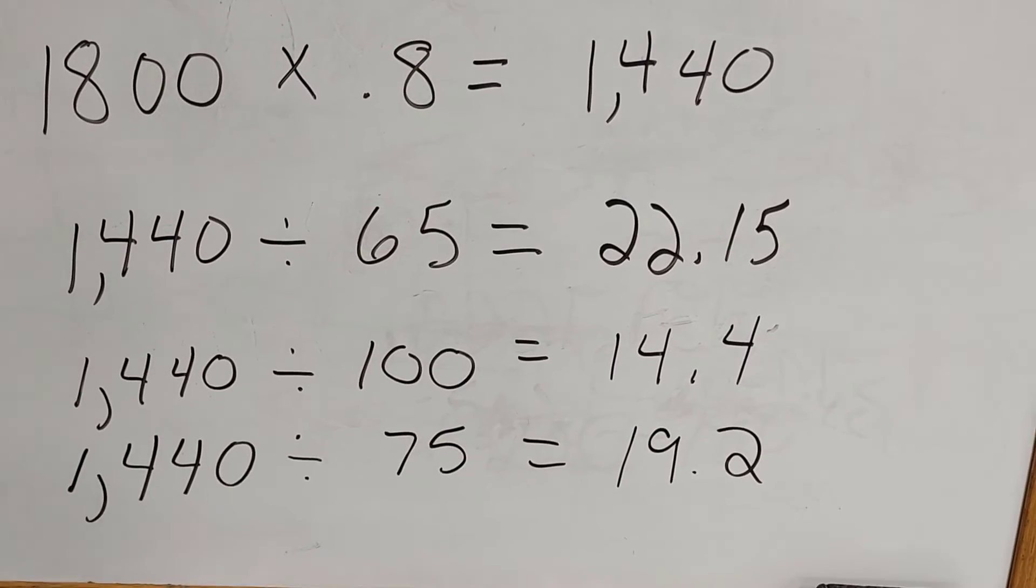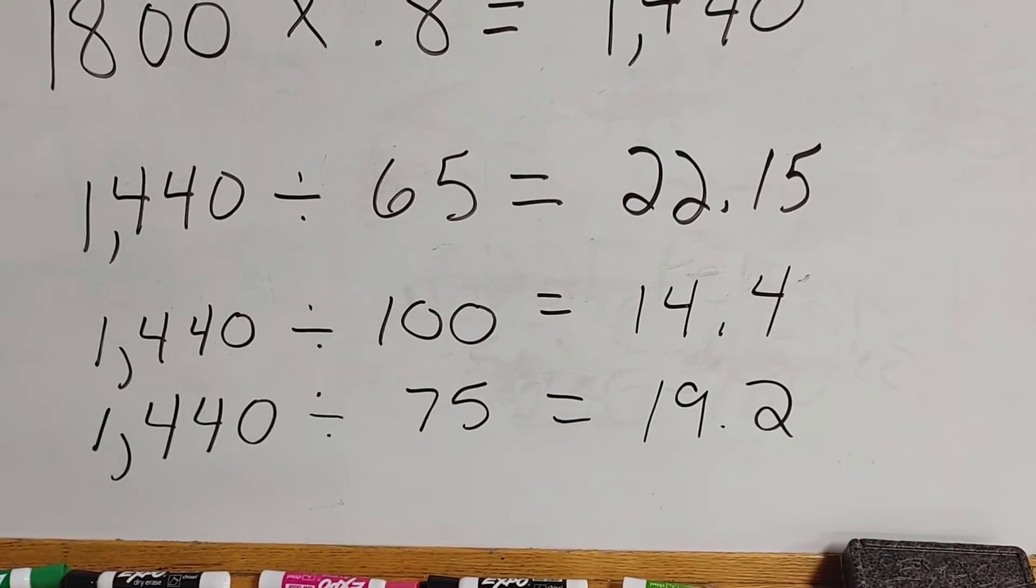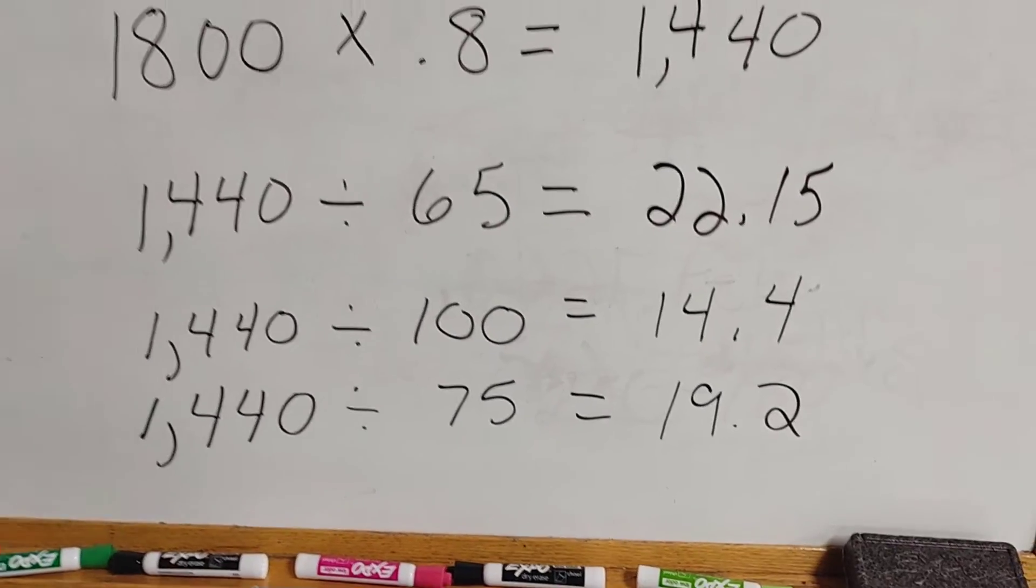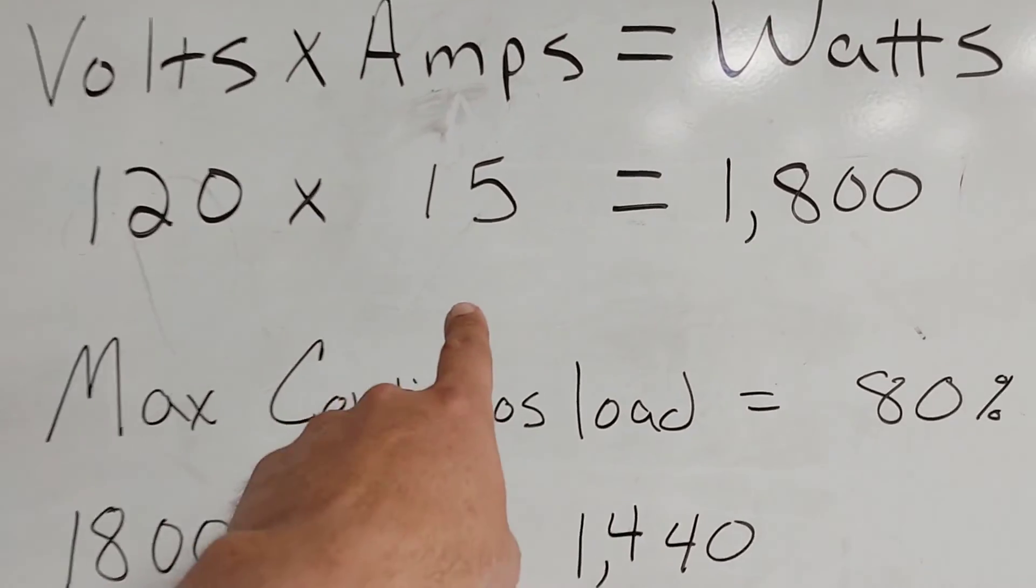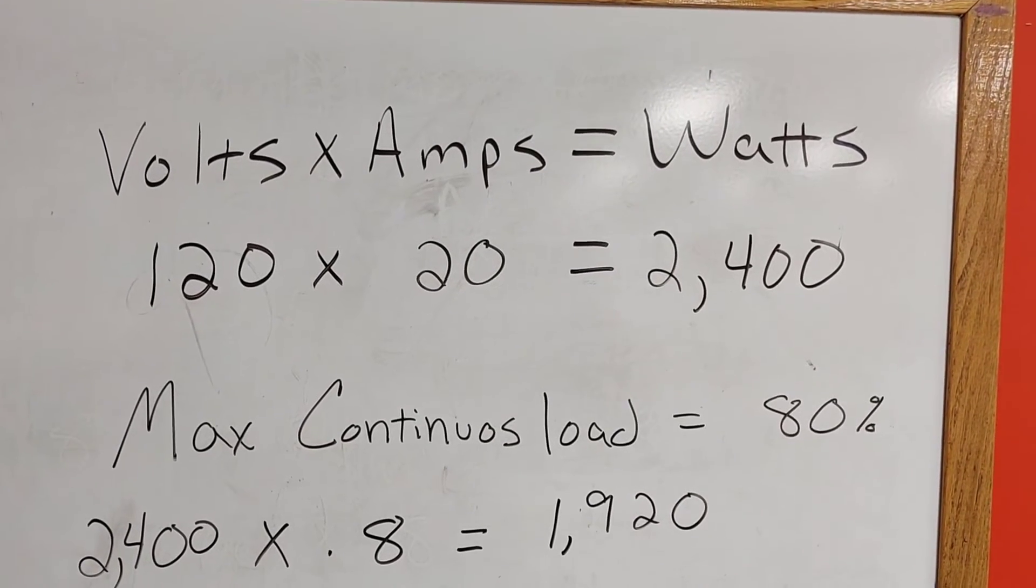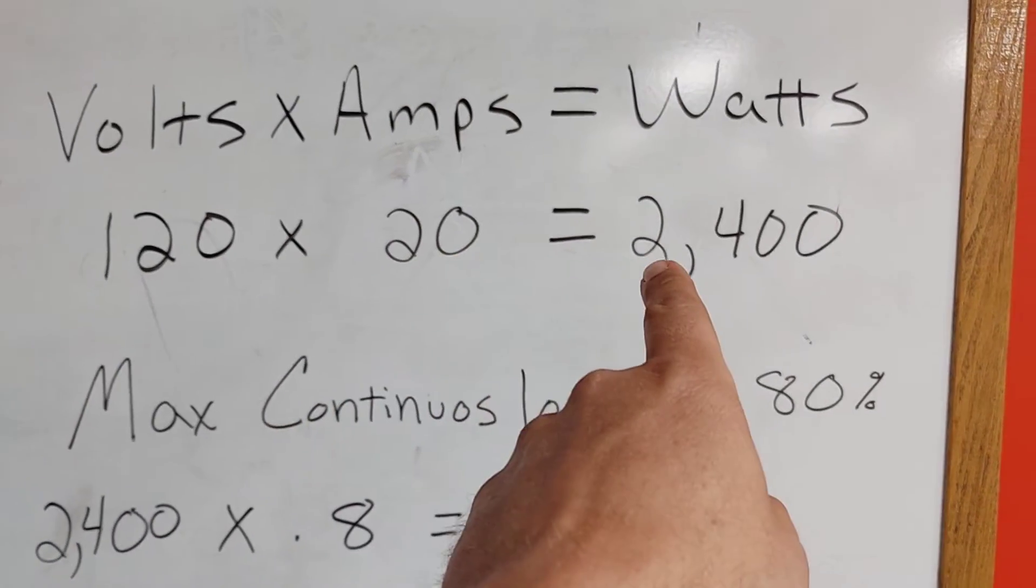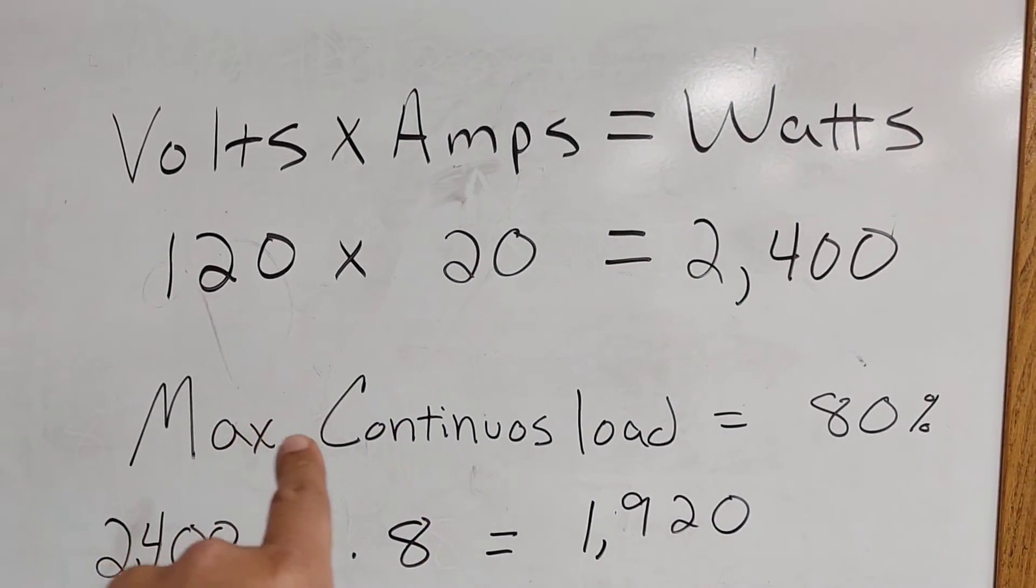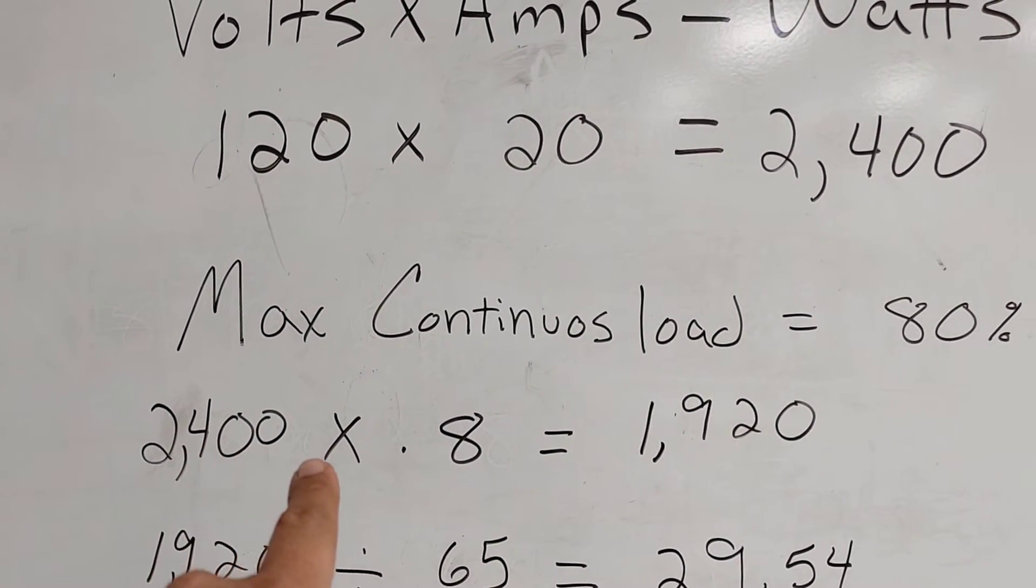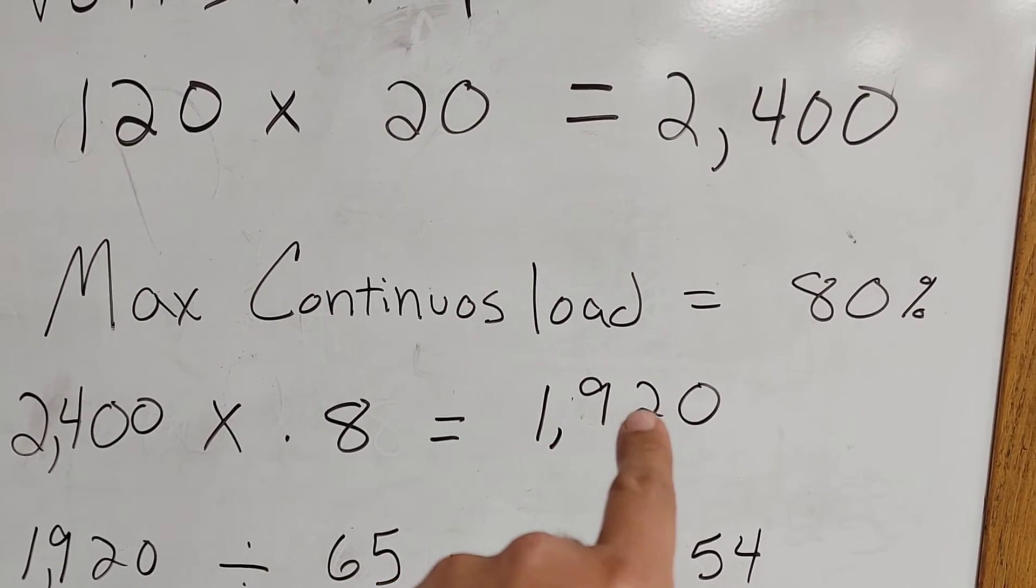Again, this is all being calculated for a 15 amp circuit. Now just to give you a quick breakdown if you were using a 20 amp circuit: 120 volts times 20 amps gives you 2,400 watts. But again, we have to apply the maximum continuous load of 80 percent. So we multiply 2,400 by 0.8, and that gives us 1,920 watts.